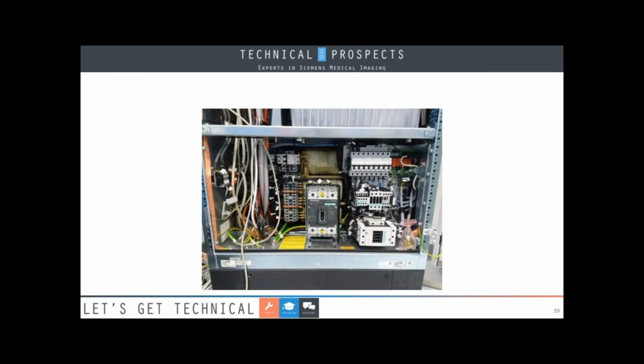One thing I did like to do is if I was lost, like here's a relay, and it's hard to see, but you can push that button in and see if you got power going in and then out. I would first measure the incoming to make sure, but if I'm not getting that relay to close, I'll use gloves because I don't want to be sparky, and then I'll just push that in. If I get power, then I'm immediately suspecting the relay. What's also good to notice though is there's usually things on top of these relays. So if you're going to order a relay, it's important to see, okay, do I have something else on top of it, or what type of relay?